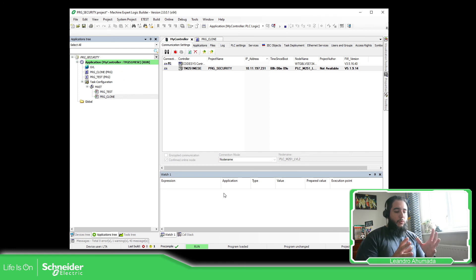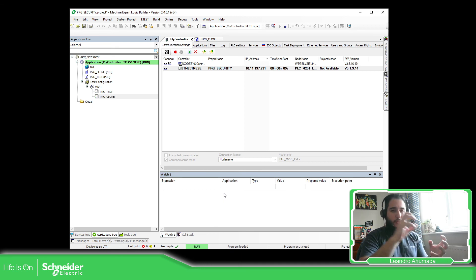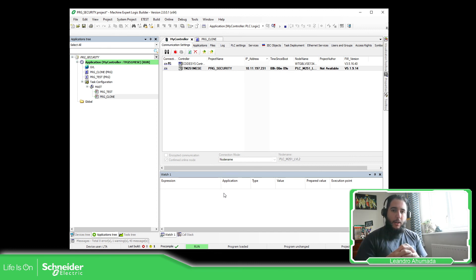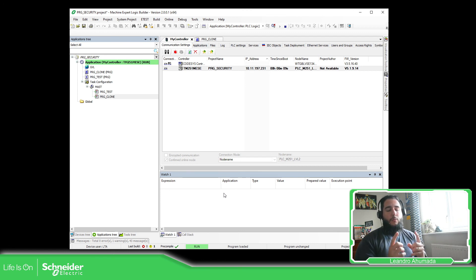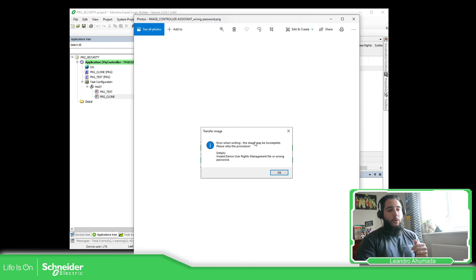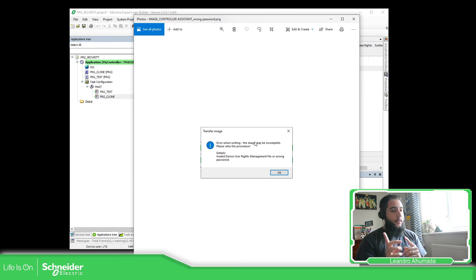In this video I have shown you how to read using the controller assistant the image of the PLC, so we can store that on our PC. Then when we have a new controller, we can open this image using the controller assistant and download it to the new PLC, so we can connect later with Machine Expert to the controller and see what's inside. It's important: if you want to use the user rights, remember the password — otherwise you're going to get an error message at the end of the image download if the password is wrong. Thank you very much for watching and I'll see you in the next one.